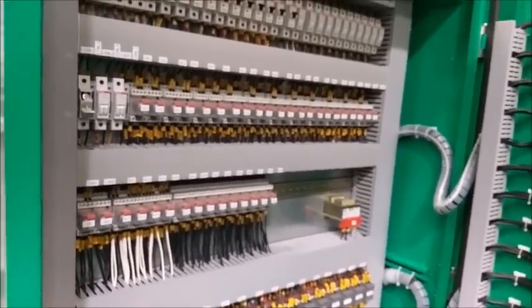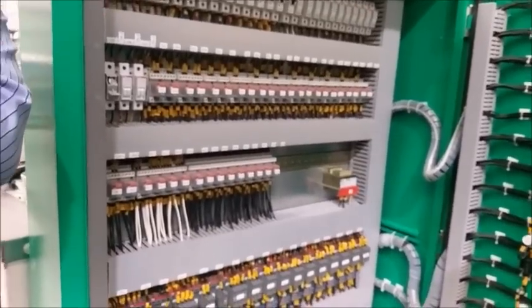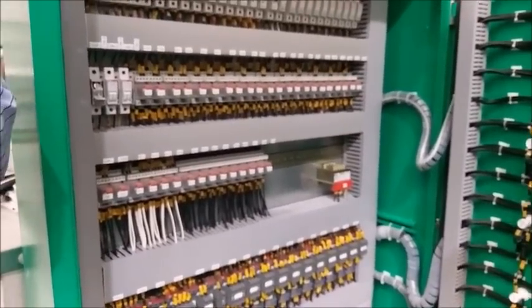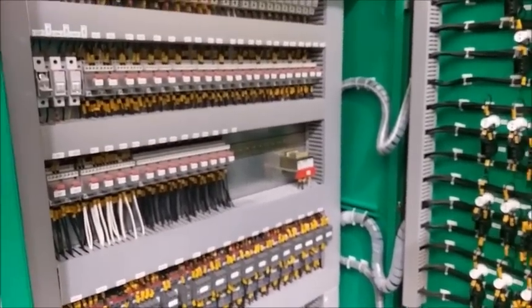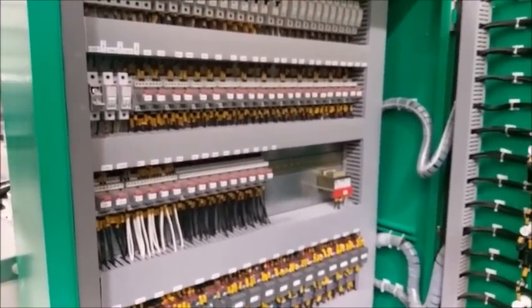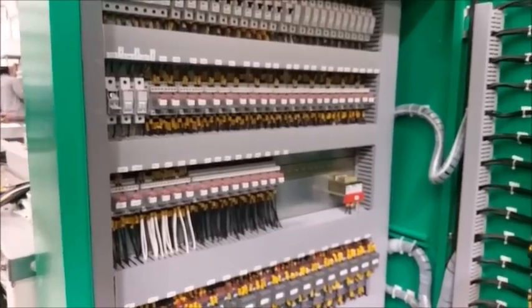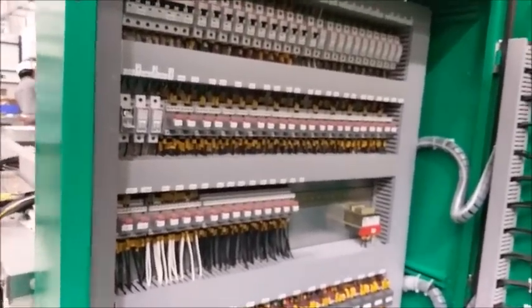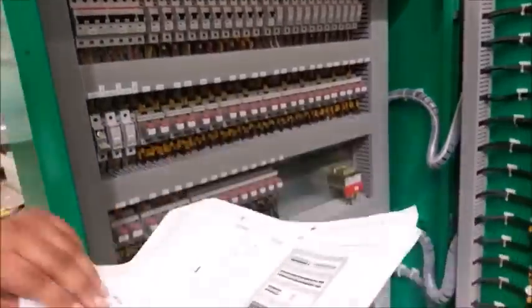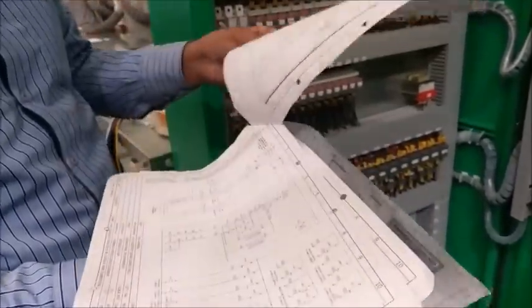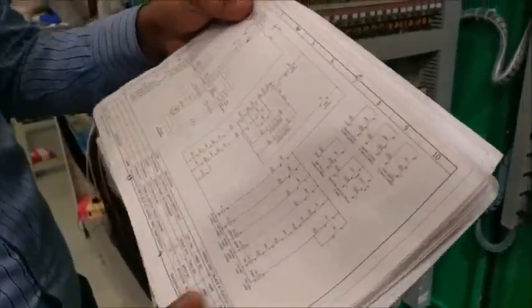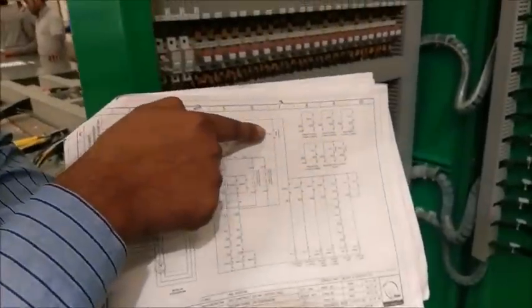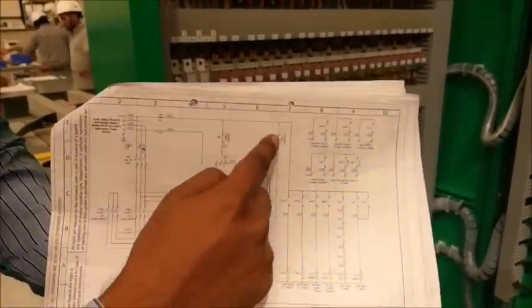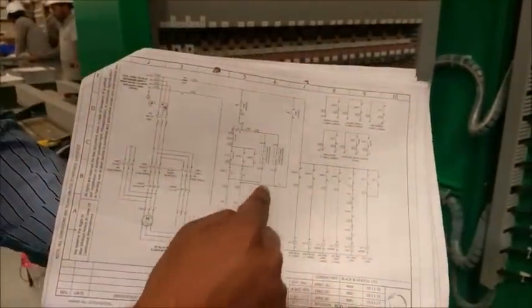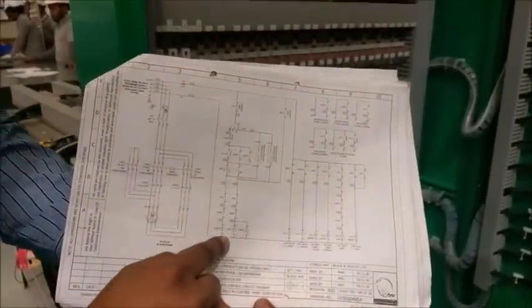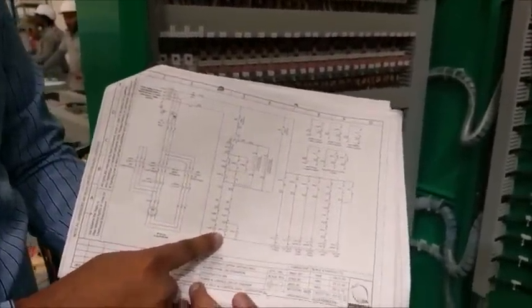Now what you need to understand: we are making integration between three systems, two systems and one panel, BMS, fire alarm, and override panel. So what procedure should be followed if there is a case of fire? The requirement was that if there is a fire, the fire has topmost priority, which will bypass all interlocks and switch on high speed for the exhaust fan. It will work on high speed during the fire.